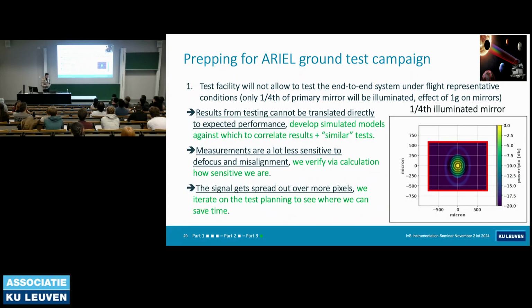And so this is not all doom and gloom, of course. So as I said, we developed those simulated models, and we perform similar tests at instrument level. What do I mean by that? Is that at instrument level, we are able to block part of the light, and then we get the same effect on the detectors, okay? And then this is kind of a similar thing that allows us to get some useful insights. The second part here about defocus and misalignment, we verify via calculation how sensitive, in fact, we are, and that will allow us to know, okay, what is our strategy then? And then finally here, it's about iterating for the test planning in terms of knowing if we need to cut some tests or spend less time on other tests. That's basically how we can approach this.